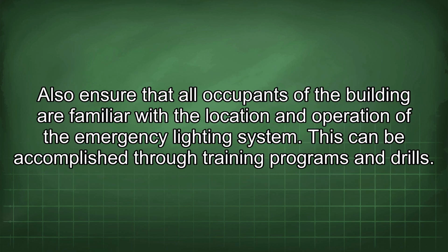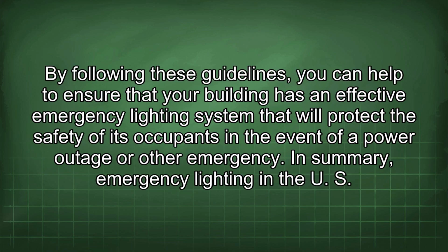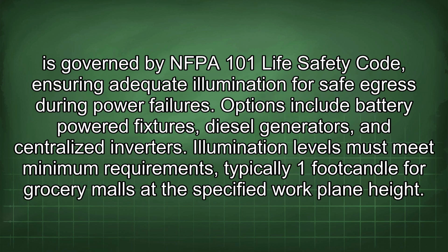Also ensure that all occupants of the building are familiar with the location and operation of the emergency lighting system. This can be accomplished through training programs and drills. By following these guidelines, you can help to ensure that your building has an effective emergency lighting system that will protect the safety of its occupants in the event of a power outage or other emergency. In summary, emergency lighting in the U.S. is governed by the NFPA 101 Life Safety Code, ensuring adequate illumination for safe egress during power failures.